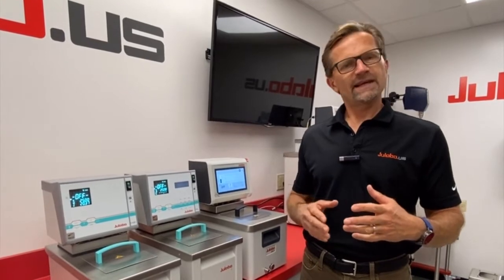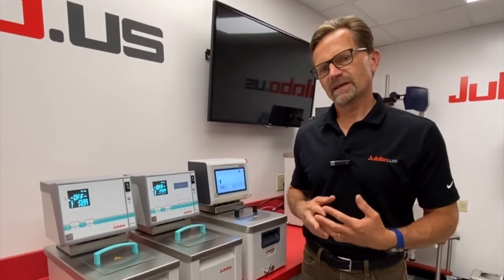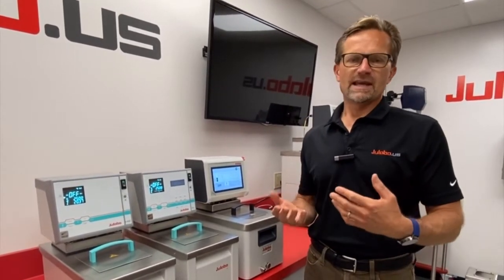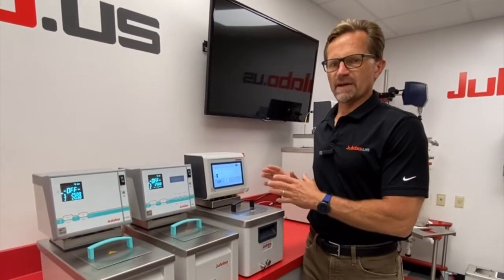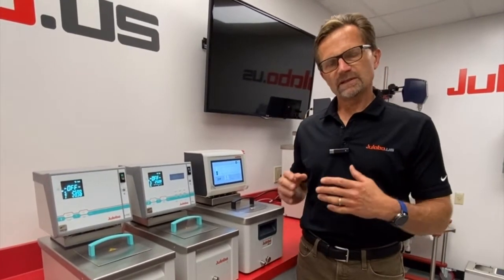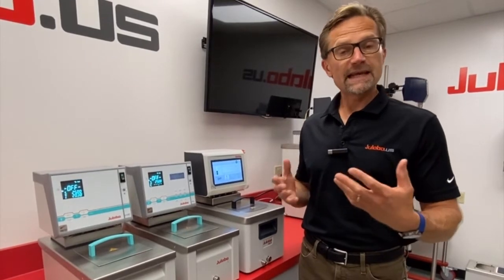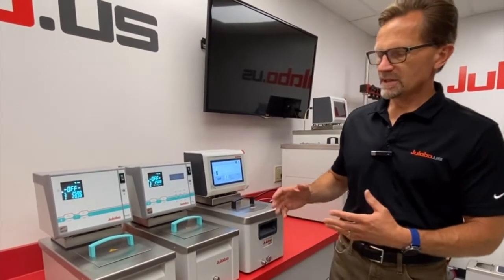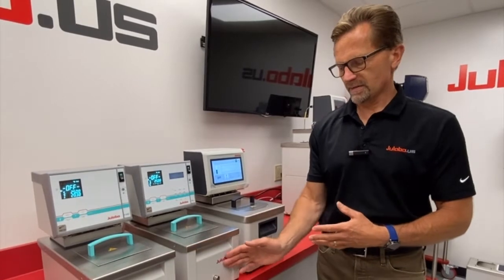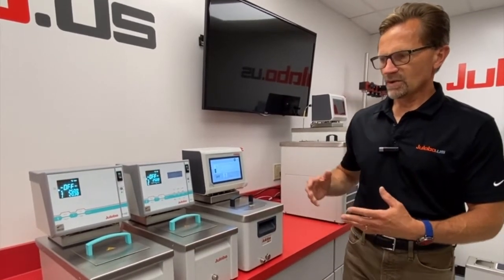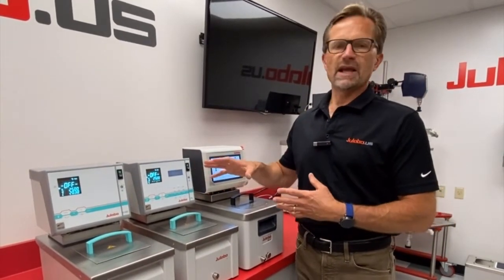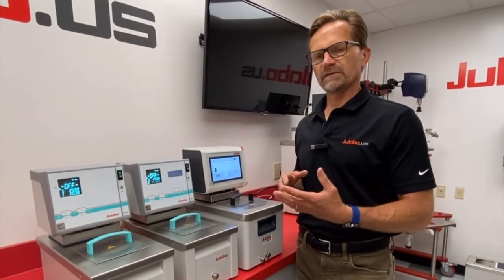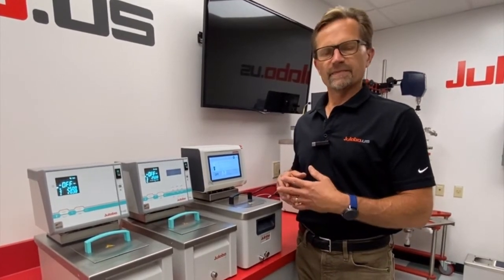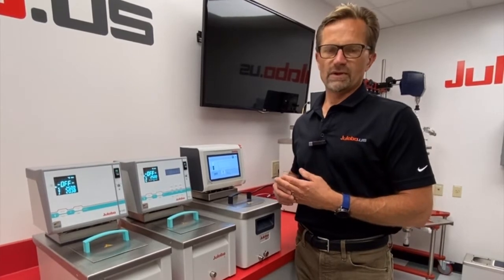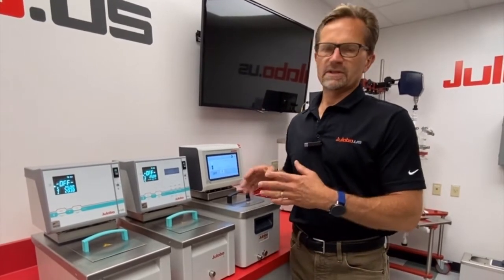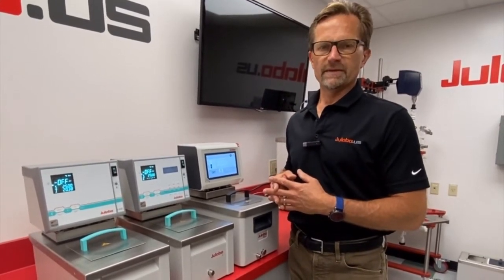And in this video, I'd like to give you an overview and comparison of the HighTech HE/HL models and the new MAGIO MS system. So these models can come equipped as heating circulators, and you can see here they can come in 4-liter bath tank systems. The HE and HL systems come in 115 volt with a 1 kilowatt heater, and 2 kilowatt heater with the 230 volt systems with the upper temperature limit of 250 degrees C.